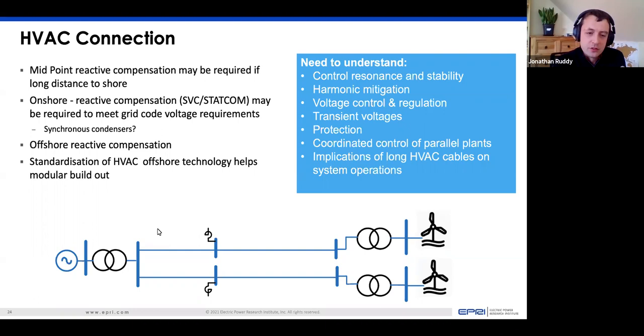There are still a number of things that we need to understand about this, particularly in the offshore network, to make sure that we maintain stability of the system, and to understand the implications of having really long AC cables connected into our onshore network. What impact does that have for transmission operators who are used to the system performing a certain way, and now things have to perform a little differently because you've got a gigawatt or 2 gigawatts of AC connected offshore wind creating different flows and different voltage issues for the system. These are all issues that can be solved, but they need to be understood and planned for in a coordinated way.